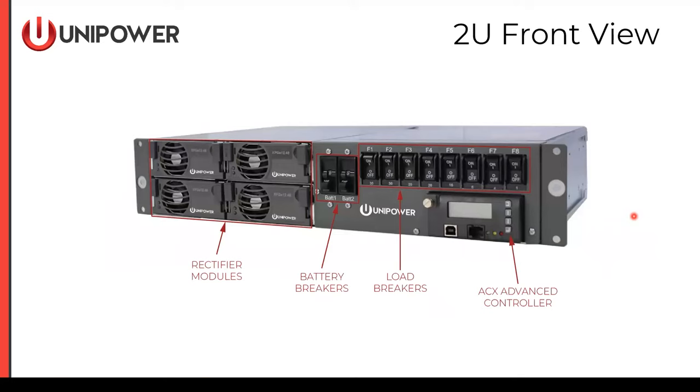Now we've moved on to the Aspiro 2U, the M23. This chassis supports up to four rectifier modules using the same 800 watt or 1,200 watt rectifier modules. Battery breakers support up to two disconnects. Load breakers have a total of eight positions utilizing the same 1 amp to 30 amp capacity breaker series, and the same ACX Advanced Controller is supported here. This can also be mounted in 19 or 23-inch relay racks.